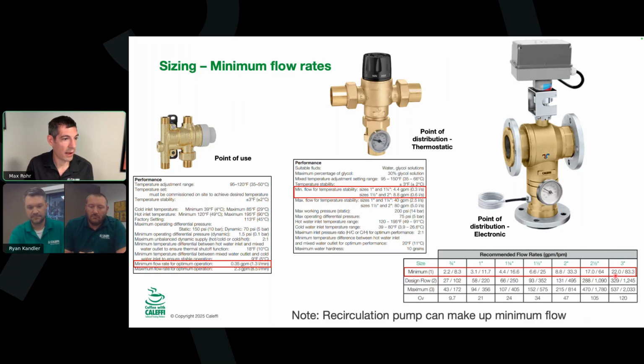So if you see an ad for a mixing valve on the market and it says it works with 0 GPM minimum flow rate, is that the full story there, or what else would you look for in that case? Yeah, if you see that statement, you should at least see a little asterisk at the end of it. If you follow that asterisk down to the footnote, it's going to say with adequate recirculation or something to that effect. We're a little more upfront in our literature where we call it a quote unquote minimum. As long as that flow rate is covered by your recirculation system, that's where that 0 comes from. So above and beyond that, 0 GPM, it's taken care of.